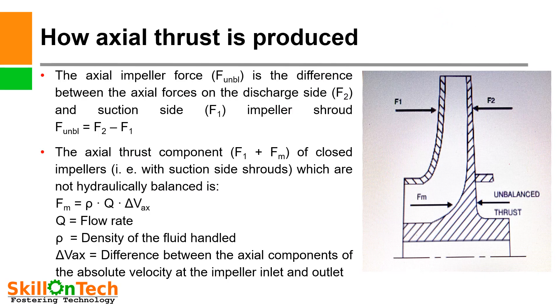How axial thrust is produced? You can see a picture of an impeller where two forces F2 and F1 are shown, and the unbalance thrust is also shown. The axial impeller force F_unbalance is the difference between the axial forces on the discharge side F2 and suction side F1 impeller shroud. Hence F_unbalance = F2 - F1. The axial thrust component Fm of closed impellers with suction side shrouds which are not hydraulically balanced is: Fm = ρ·Q·ΔVax.